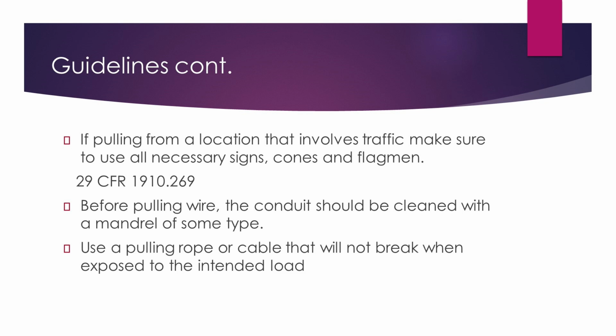And if you have any kind of rigid metal conduit, if you have water—and I'm telling you right now, I've never seen any conduit without water in it, it just happens, especially at dip poles, takeoff poles, underground poles, whatever you want to call them—anytime you see stuff like that, you need to make sure there's no rocks and debris down in there. Because when water gets in there and freezes, it'll physically force those rocks and debris into that cable, like cutting into it. So just know that doesn't need to be in there. Make sure you get it cleaned out.